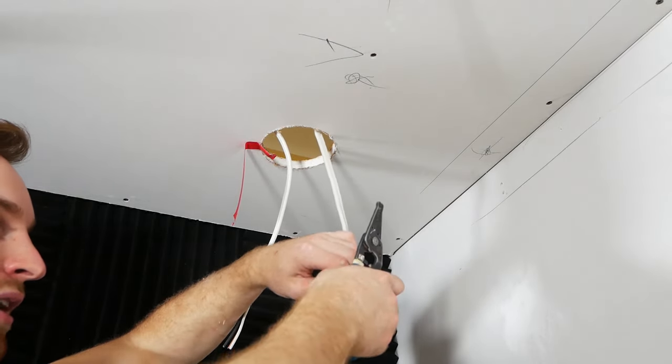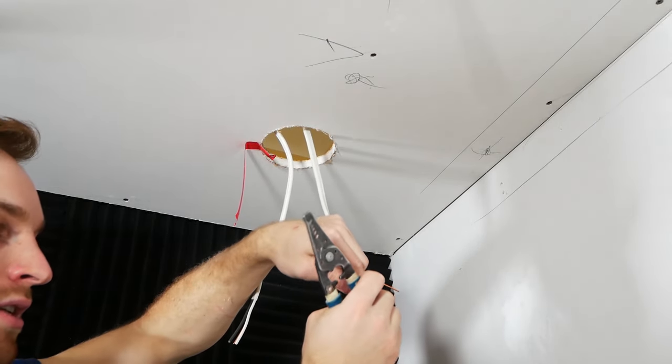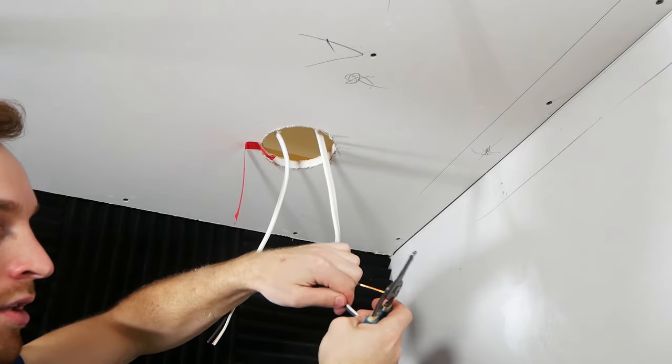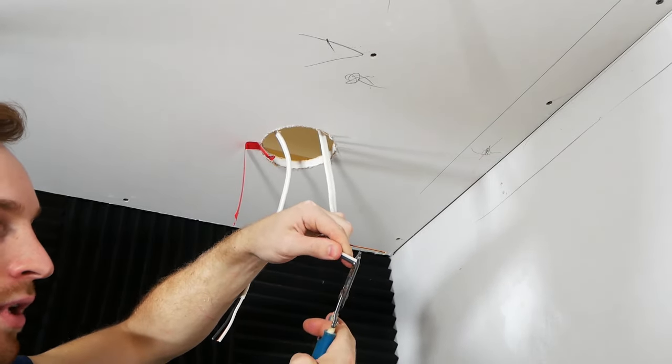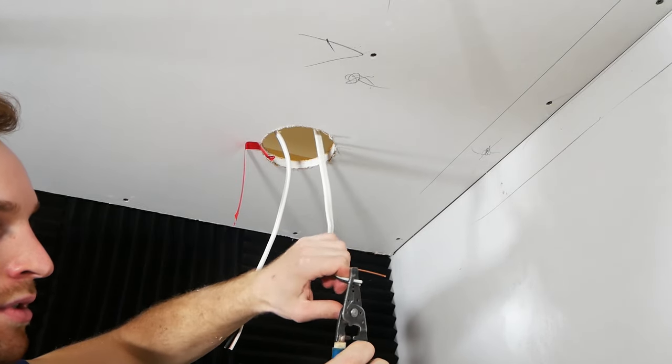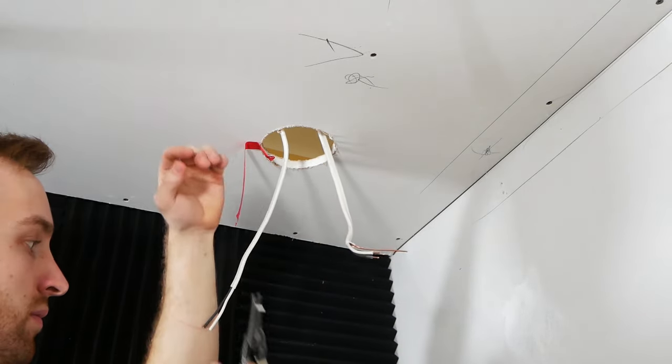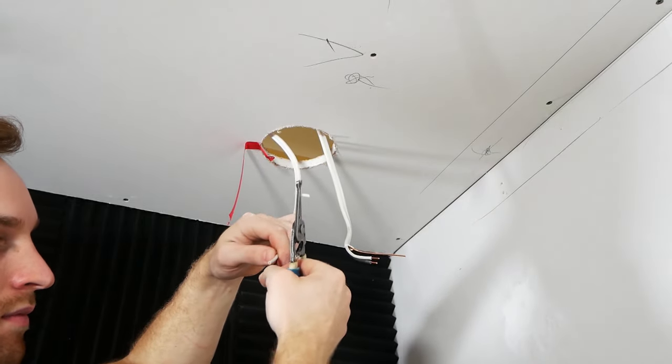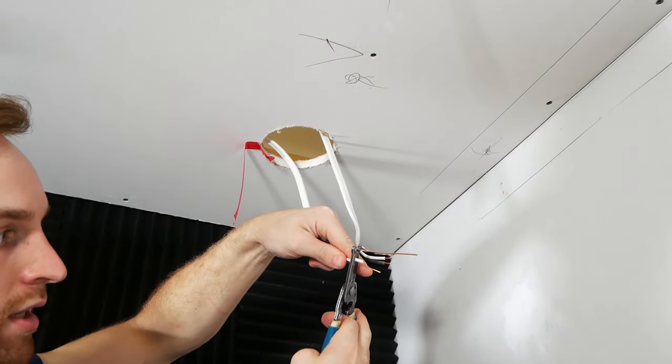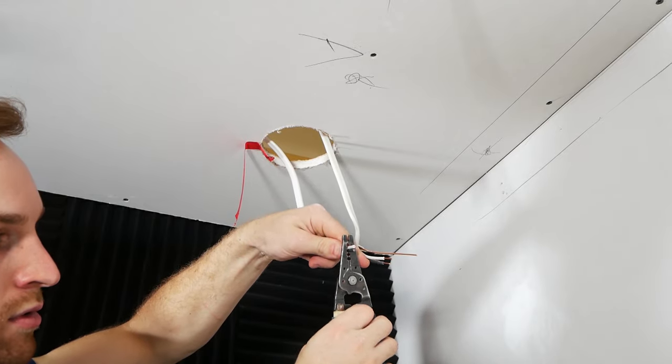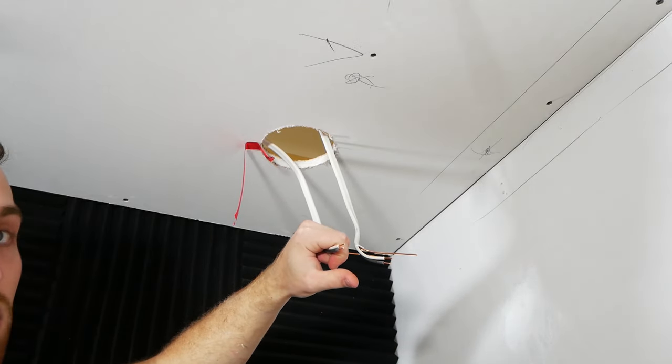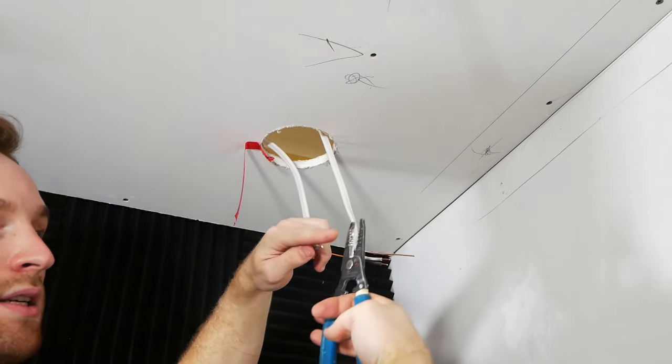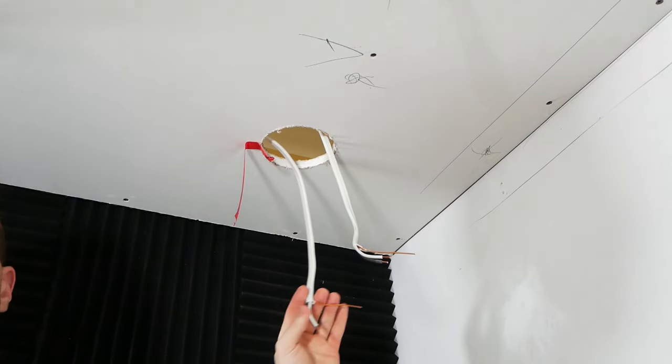And strippers, depending on what gauge you're using, I'm using 14, so I'm going to use the slot that says 14 solid. Again, you can go a size up, so I can do 14 and 12, and just do both at once. 14 and 12 solid. Never go a size down though, we wouldn't want to use the 16, because then we would damage the copper.